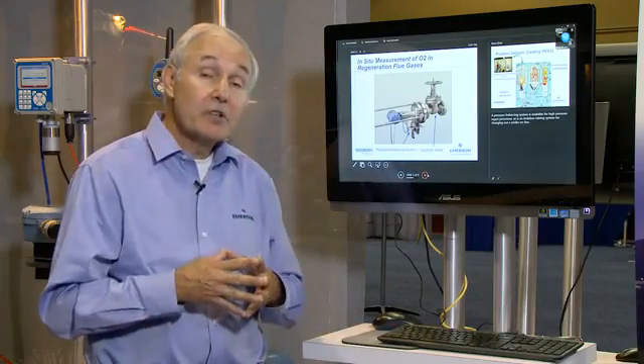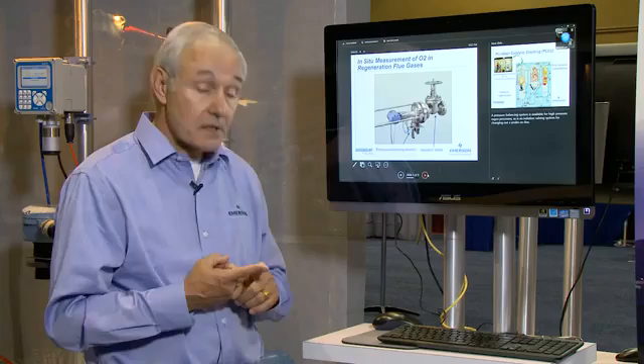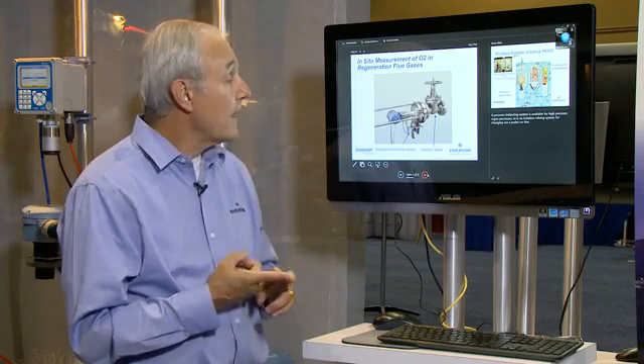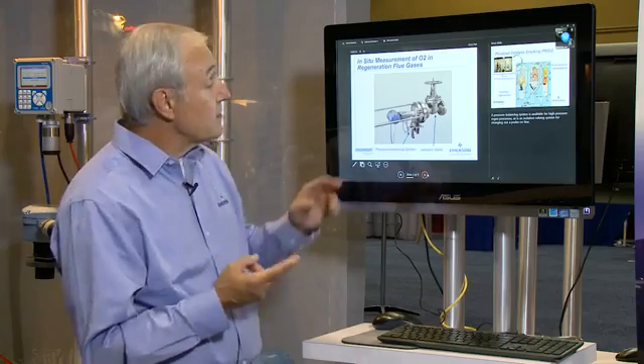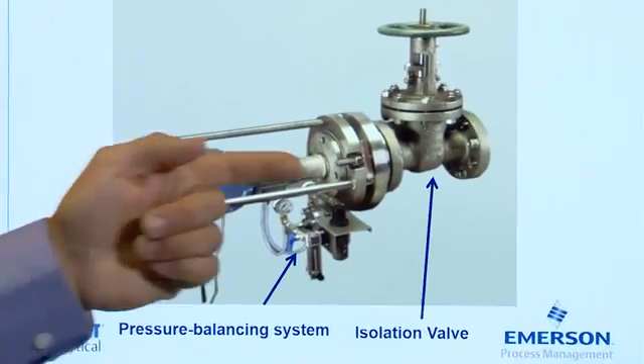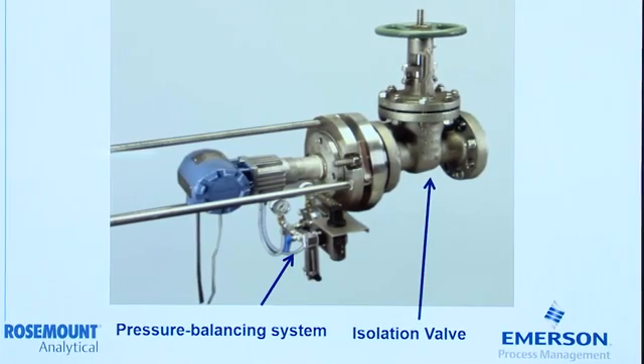There are a couple challenges when we do this. A lot of times these regeneration units operate at a higher pressure, and with an in situ type of product, if you have an instrument failure, you may have to get it out while the process is running under pressure and under temperature.